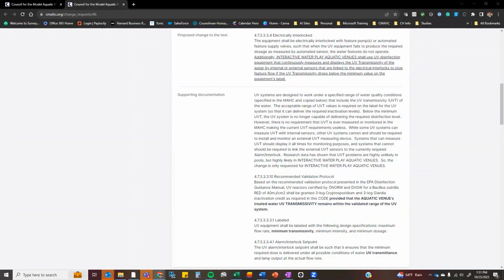And am I understanding this correctly, that this is basically measuring whether the UV light is able to transmit into the water? So it's basically checking for cloudiness in the water, or calcification or clouding on the tube that would prevent the light from transmitting into the water, and we're shutting it down based on there not being enough light getting in contact due to blockage.